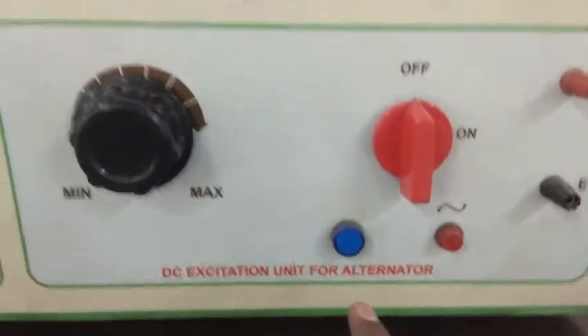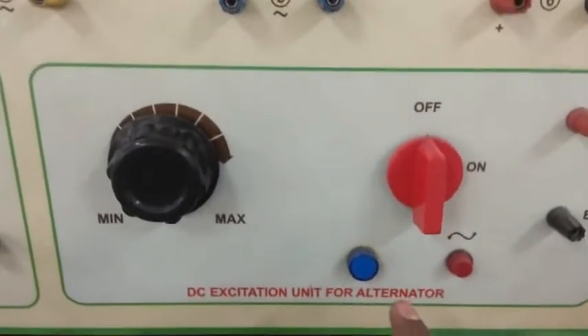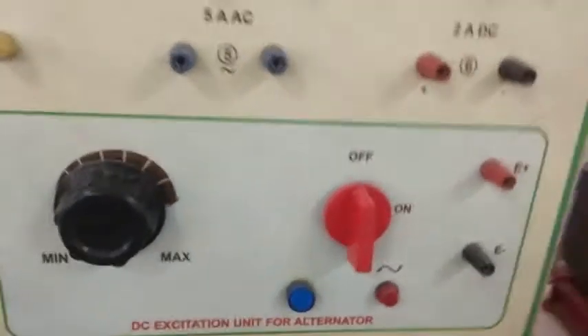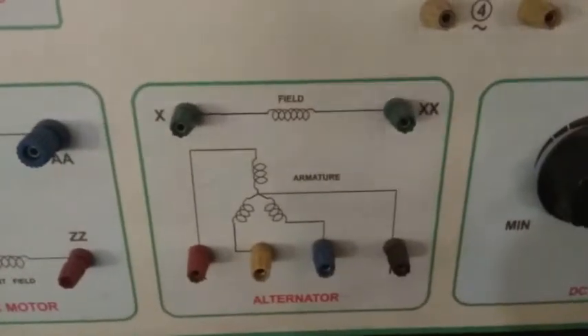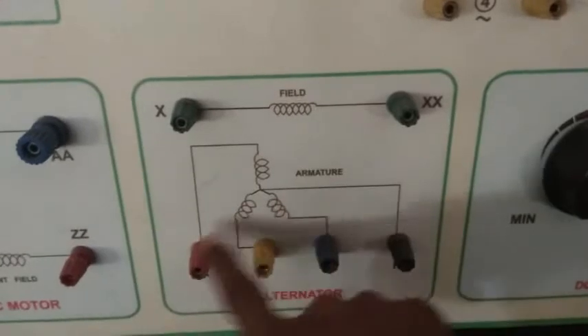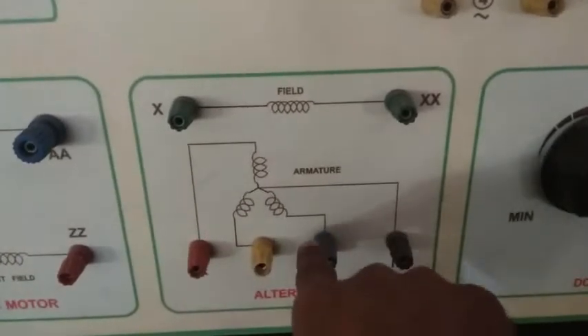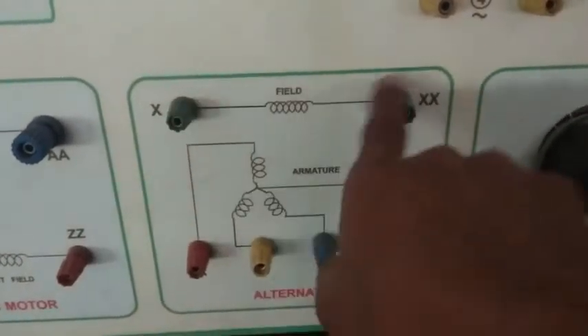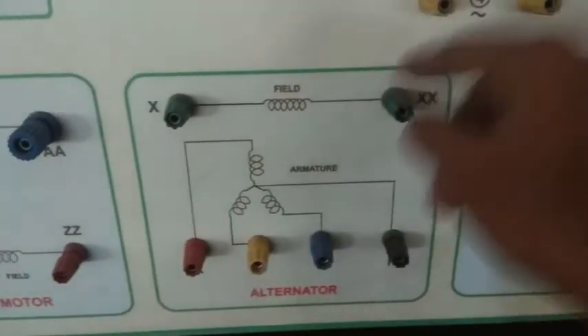And this is the DC excitation unit. With the help of this, we will give the excitation to the field winding of the alternator. Beside this, here is the terminal of the alternator on the panel. This is the terminal of the alternator, a star connected alternator. It is R, Y, B, and this is a field terminal of the alternator.